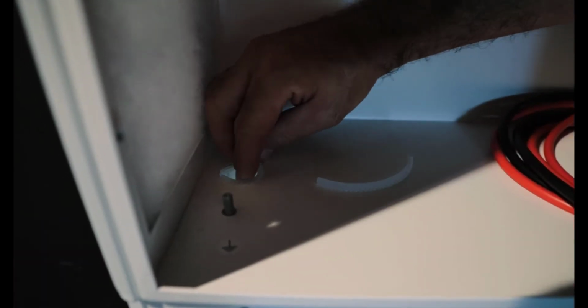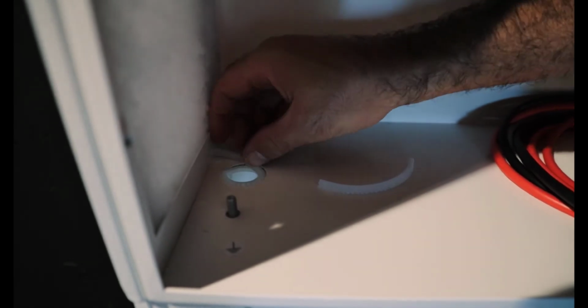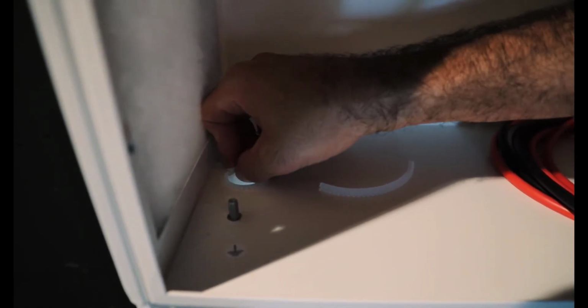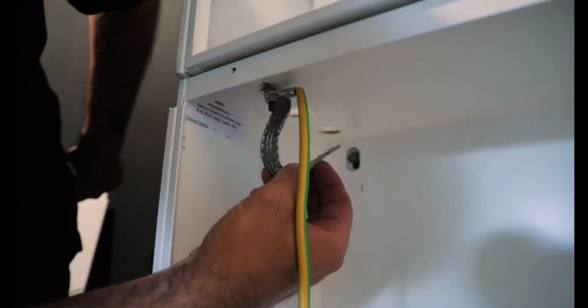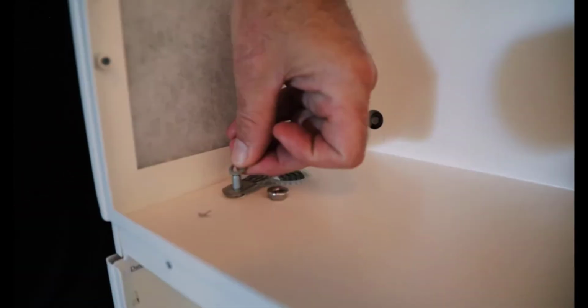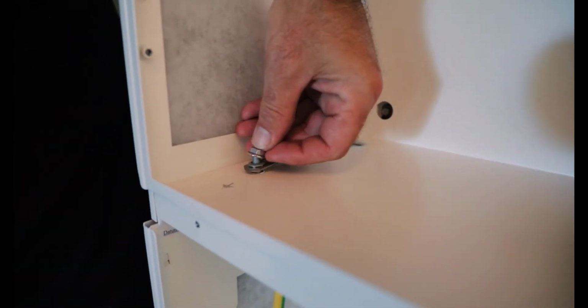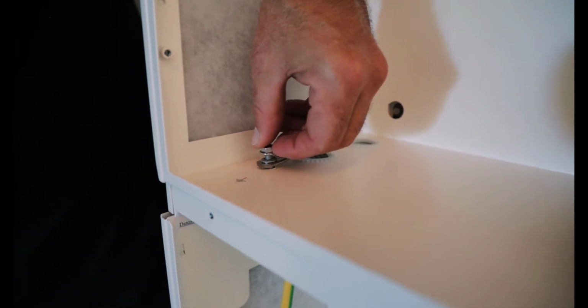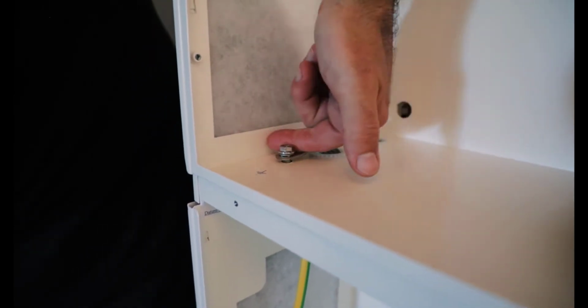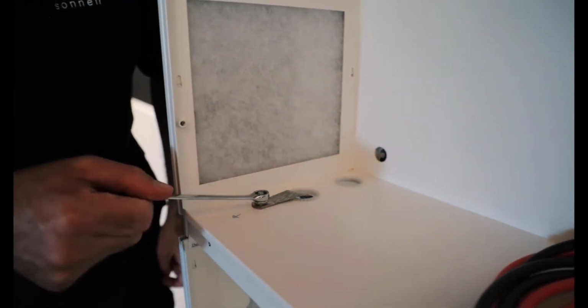Now there is access between the extension housing and the main unit. You get two little plastic clip-on strips which need to be positioned around the edge of those openings to ensure that there's no ever chafing of the cables. And then what we do is we pass the braided earth strap between the extension housing and the main unit to ensure that we have earth continuity. This is purely equipotential bonding, but it's a very important feature of the Sonnen system that everything is earthed back to the same base value.